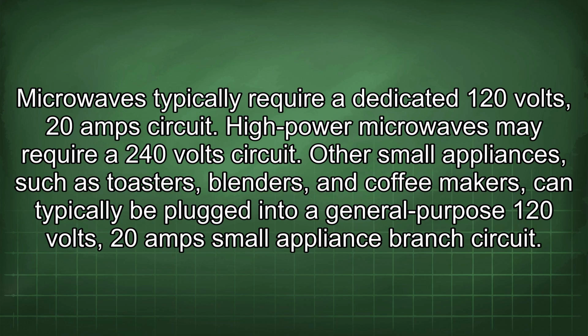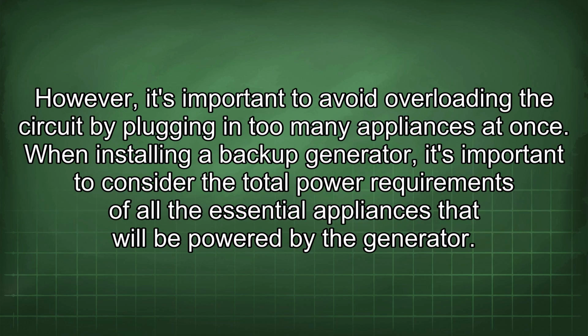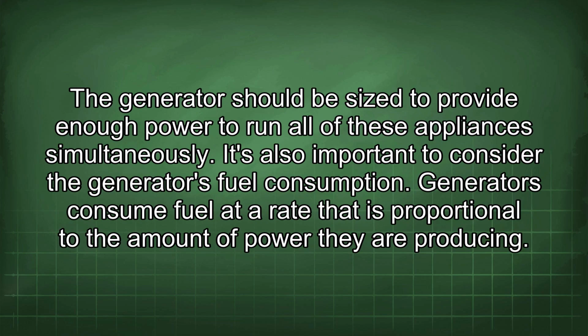Other small appliances, such as toasters, blenders, and coffee makers, can typically be plugged into general-purpose 120 volts, 20 amp small appliance branch circuit. However, it's important to avoid overloading the circuit by plugging in too many appliances at once. When installing a backup generator, it's important to consider the total power requirements of all the essential appliances that will be powered by the generator. The generator should be sized to provide enough power to run all of these appliances simultaneously.